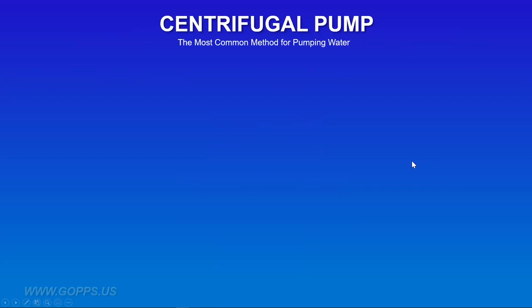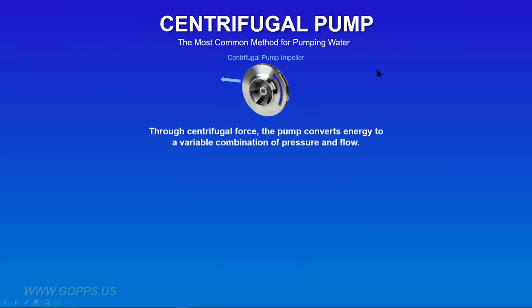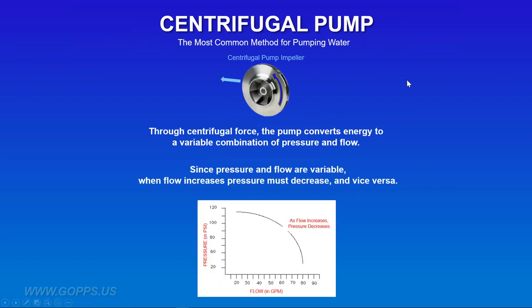Centrifugal pumps are the most common method of pumping water in the world. A centrifugal pump uses an impeller to move water. Through centrifugal force, the pump converts energy to a variable combination of pressure and flow. Since pressure and flow are variable, when flow increases, pressure must decrease and vice versa. That's important to understand, because what we're looking at here at the bottom of the screen is what's known as the pump curve — the most important thing in the pump world. People sometimes fully understand it and sometimes aren't sure what it's all about, but it's relatively simple and very important for pump selection.